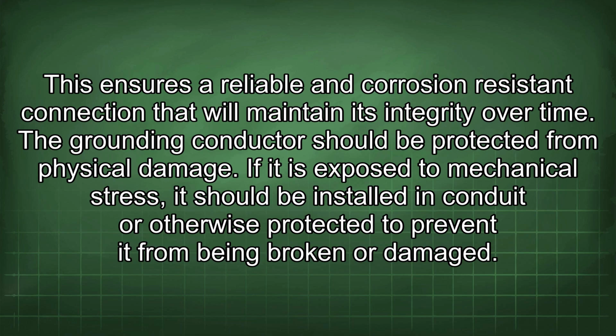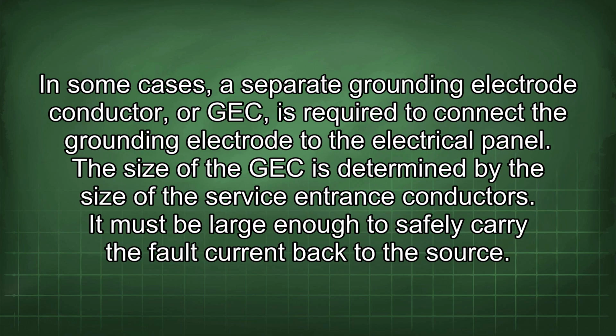The grounding conductor should be protected from physical damage. If it is exposed to mechanical stress, it should be installed in conduit or otherwise protected to prevent it from being broken or damaged. In some cases, a separate grounding electrode conductor, or GEC, is required to connect the grounding electrode to the electrical panel.